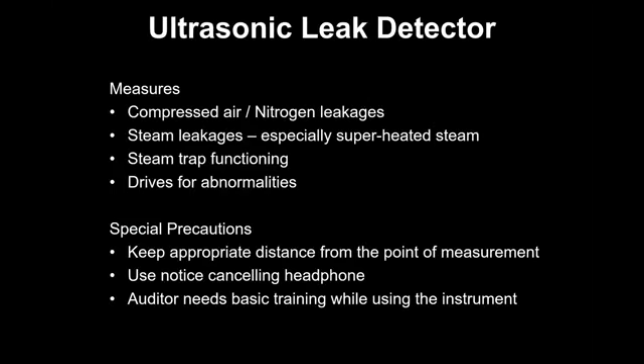These are some instruments used for leak detection. This is a very good instrument actually, and we are using it extensively now. It is basically to determine if there are any leakages in a compressor or nitrogen line, because compressor leakages are very difficult to gauge. All said and done, a plant is a very noisy place. You already have multiple noises, so you will not be able to hear the noise of a compressor leak. But this ultrasonic leak detector can detect and identify a leakage through noise.